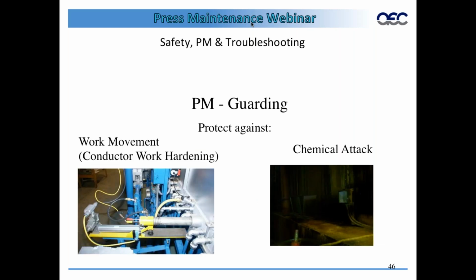Another area of guarding involves wiring, for when you have moving devices, doing the best you can for conductors moving back and forth. Copper especially tends to work hard easily, as do some other alloys. You see a thermocouple there, and that movement can be one of the largest problems on a system, going back and forth until it finally breaks, becoming a regular maintenance task. So always look for ways to reduce the wires from moving back and forth.